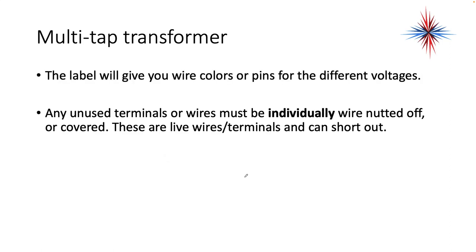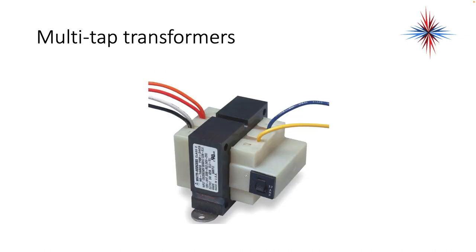The label will give you the wire colors and pins for the different voltages. Any unused terminals or wires must be individually wire nutted off or covered — these are live wires and terminals and they can short out. Don't put the additional wires under the same wire nut; they have to be individually wire nutted off or you're going to short the transformer. If you're just using this for 120 volts, you're going to use the black and white and cap off the two additional wires. My blue and yellow are my low-voltage side — you're going to be using those.